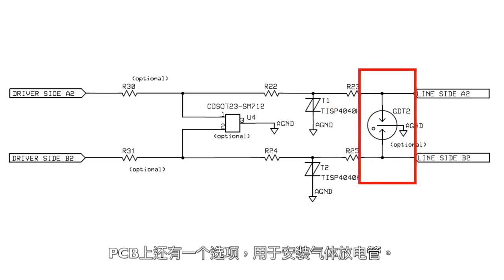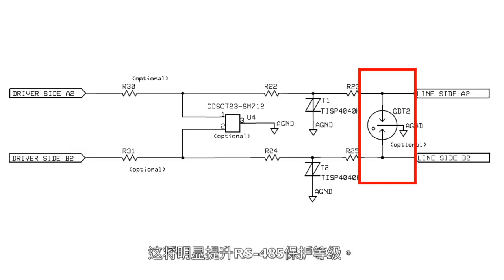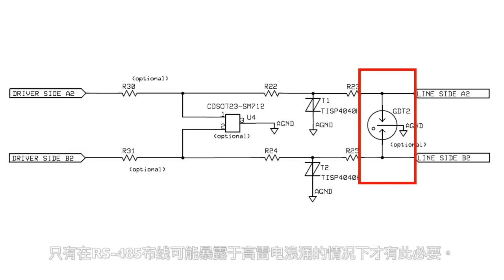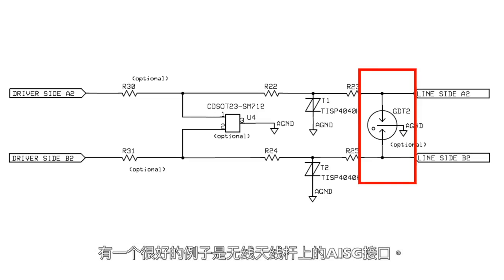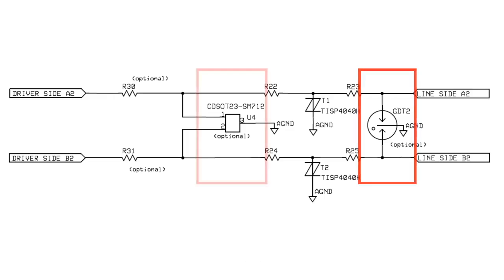An option exists on the PCB to also mount a gas discharge tube. This would significantly enhance the robustness of the protection for RS-485. It is only necessary in those circumstances where the RS-485 cabling could be exposed to high levels of lightning surge. A good example would be an AISG interface on a cellular radio mast.